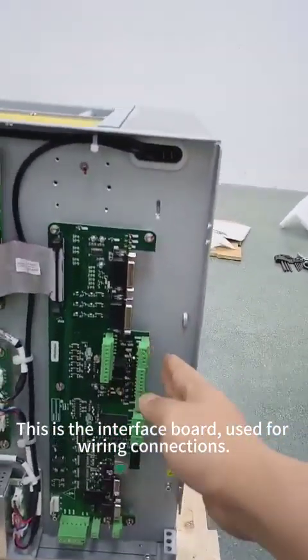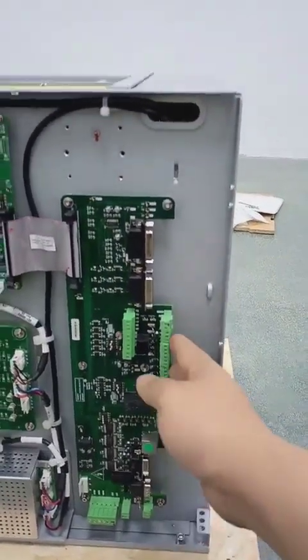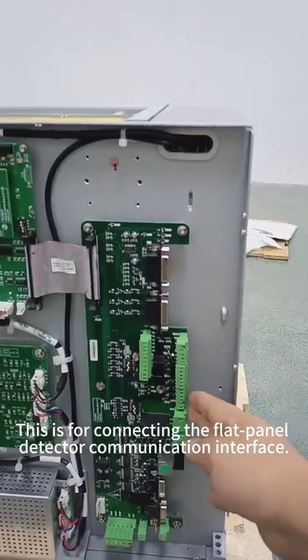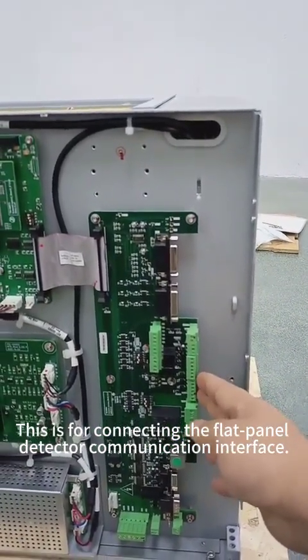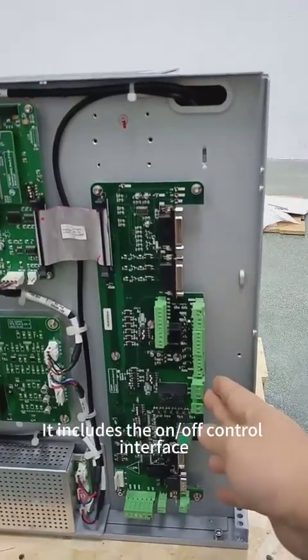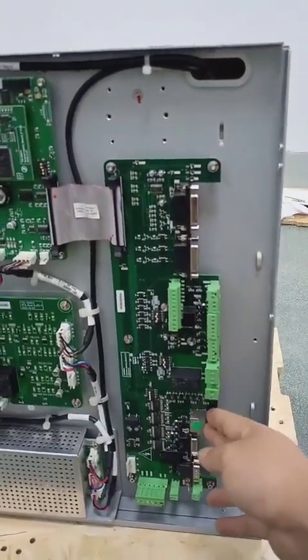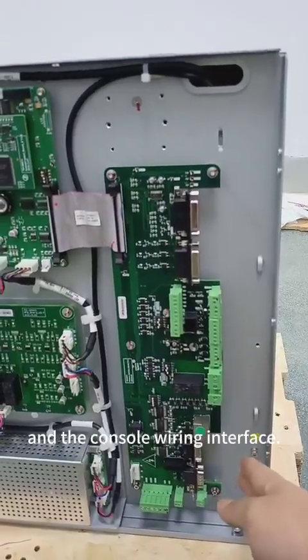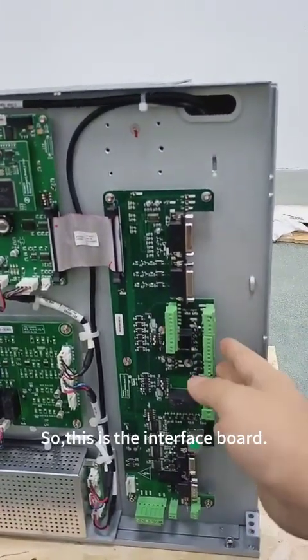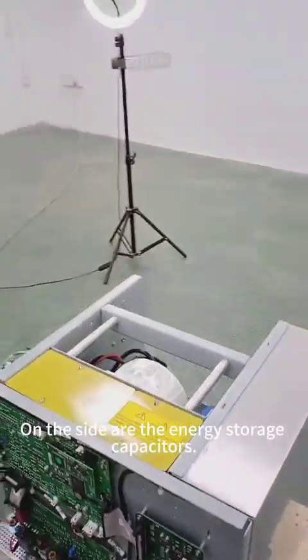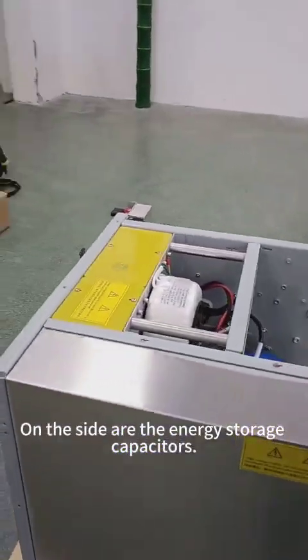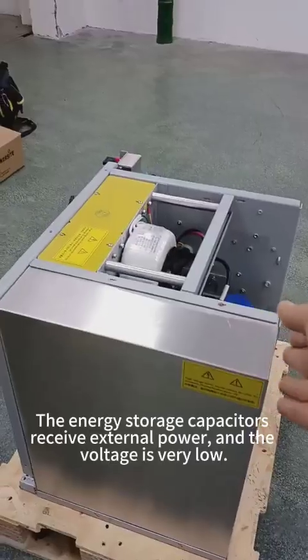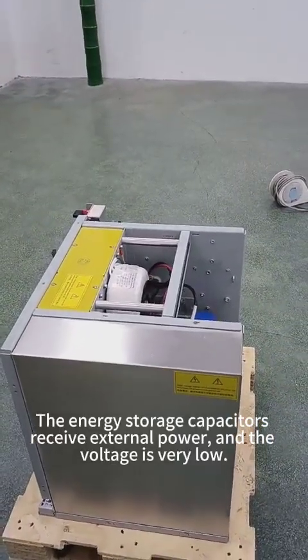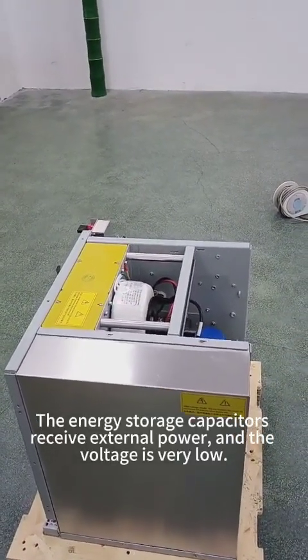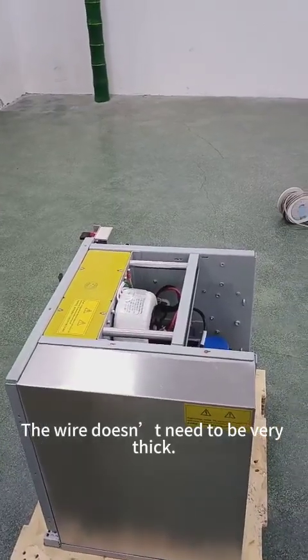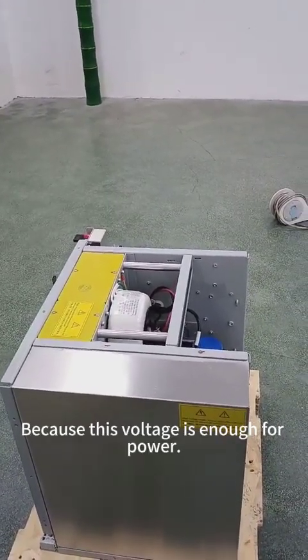This is the interface board used for wiring connections. This is for connecting the flat panel detector communication interface. It includes the on and off control interface and the console wiring interface. So, this is the interface board. On the side are the energy storage capacitors. The energy storage capacitors receive external power, and the voltage is very low. The wire doesn't need to be very thick, because this voltage is enough for power.